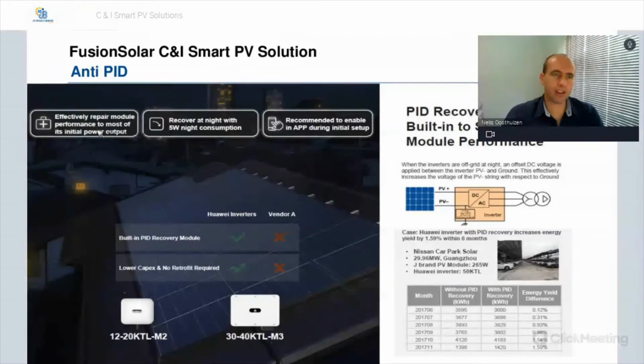The Huawei AntiPID effectively repairs the module performance to most of its initial power output. The recovery is done at nighttime with less than 5 watt night consumption. We do recommend that you enable this in the app during your initial setup. But of course, if you do not wish to use this function, you can have it disabled if you really want to save that 5 watt consumption at night. It's also a function that can be added later on. So if you pick up some problem on your panels and you believe that the PID effect can have an effect on it, you can always enable it at a later stage.